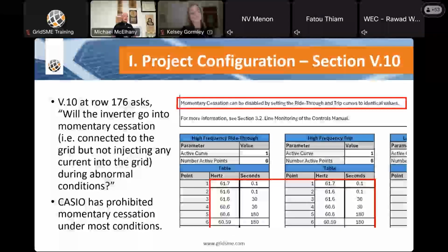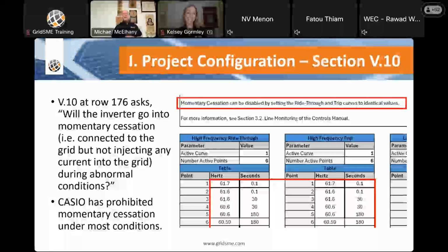All right, so now getting into more of the meat of it. One of the questions at V.10 is, will the inverter go into momentary cessation? As you heard from Kelsey, one of the requirements of Appendix H is that momentary cessation is not allowed. It's allowed in very, very rare conditions, only on overvoltage conditions, but it's generally not allowed. CAISO has prohibited it under most conditions.